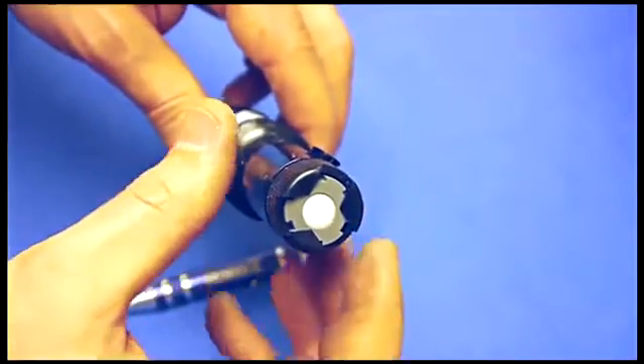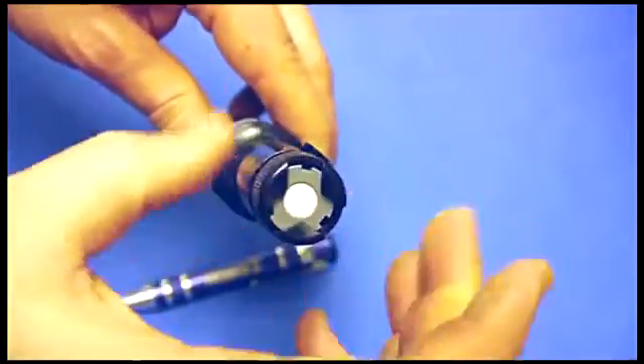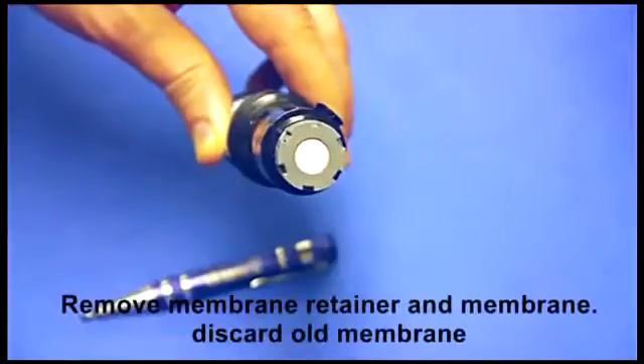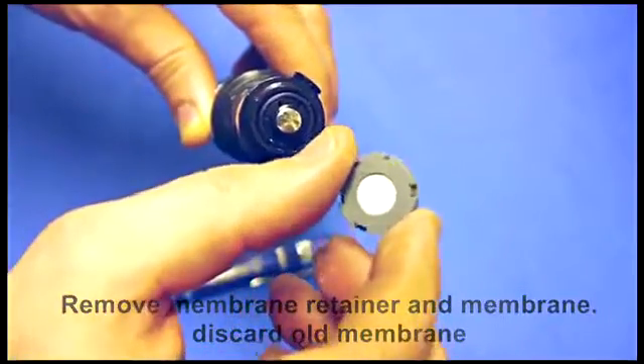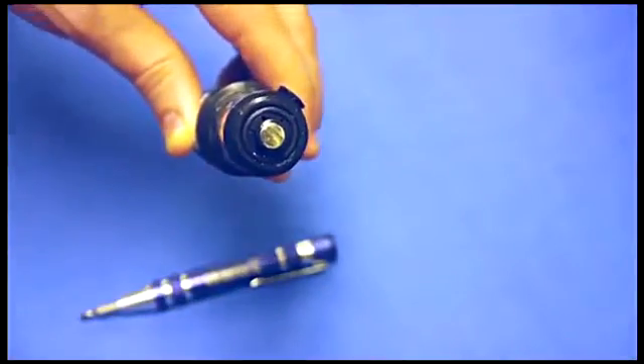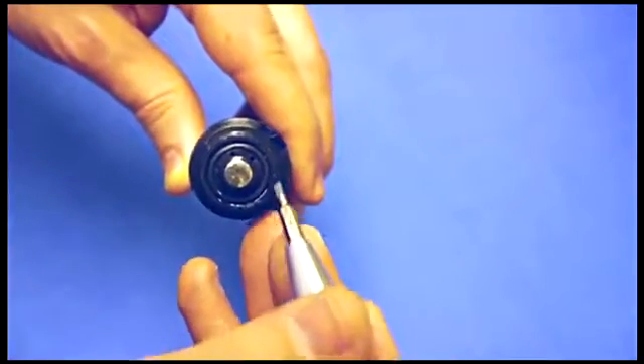The first thing you want to do is remove the membrane assembly. First take off the membrane retainer, then you can discard this membrane head and throw that away as it's been used. The last thing you want to do is remove the o-ring.